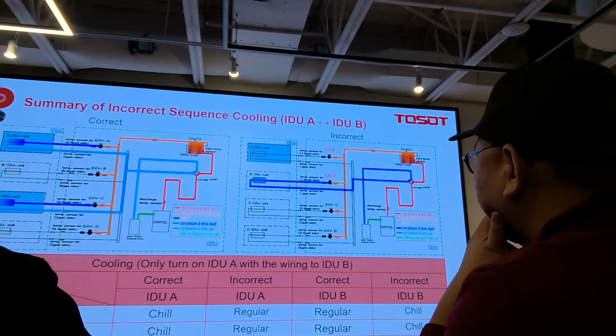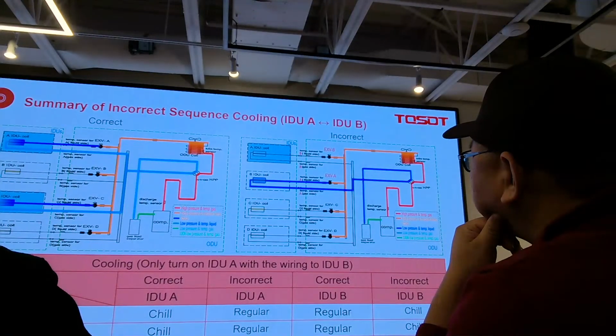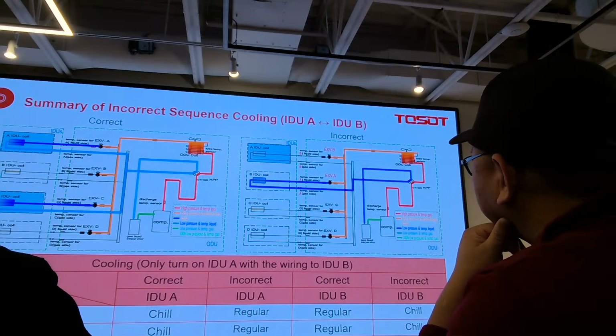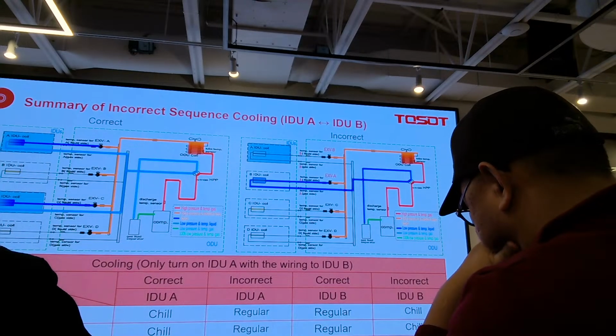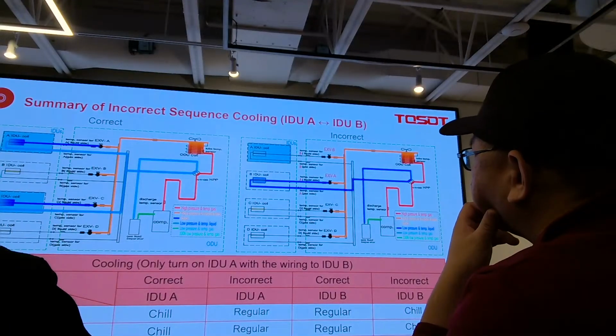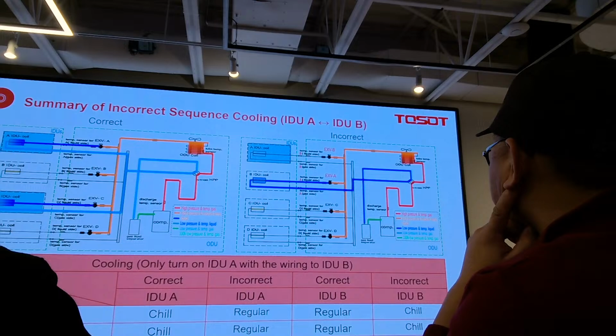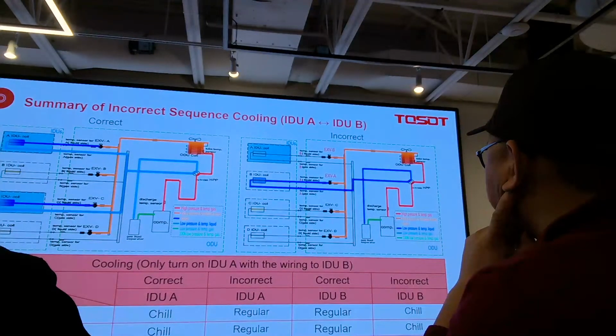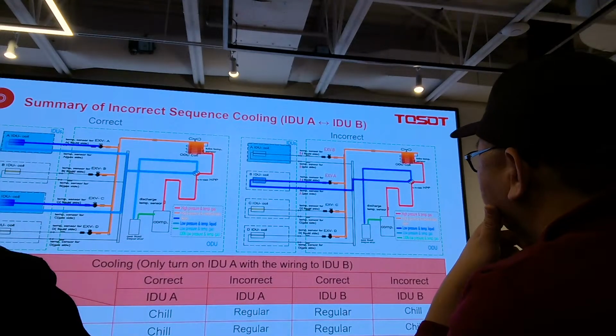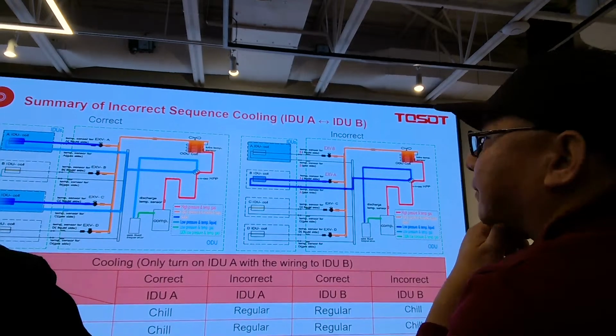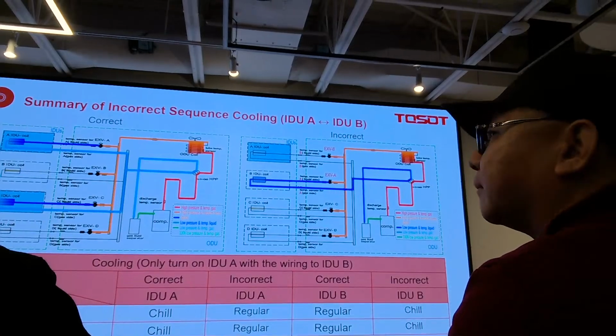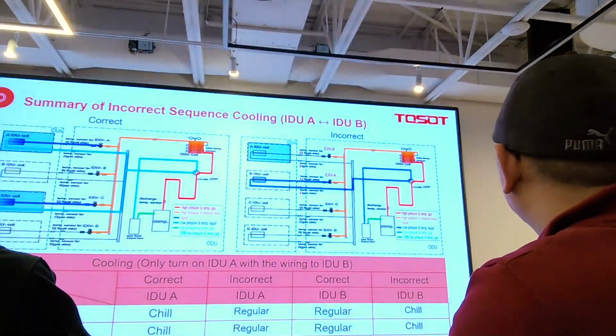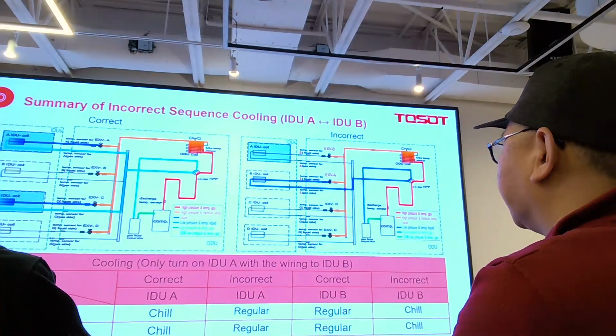Yes. So about the whole units, is it possible to have some units provide cooling and some units provide heating? No. That function is called heat recovery, simultaneous operation. It's not possible, even for the VRF mini, because there is not enough space. We have the heat recovery series, and also the heat pump series. This simultaneous cooling and heating is only for the heat recovery series. Do they have two compressors? No, we have the branch box. The branch box selects whether this pipe, this branch, is for cooling or heating. Yes.